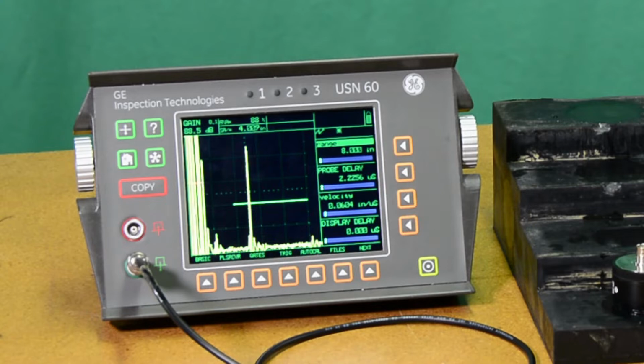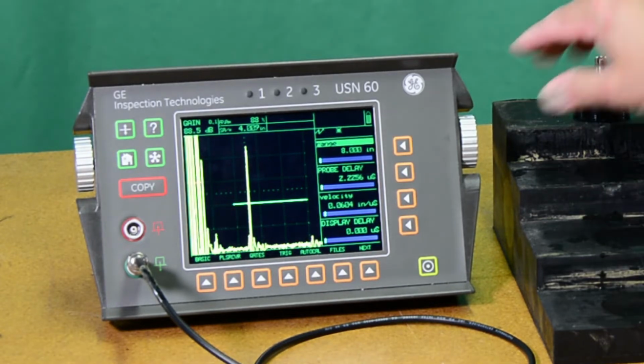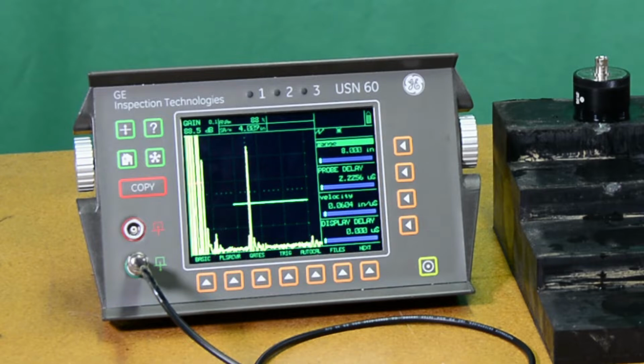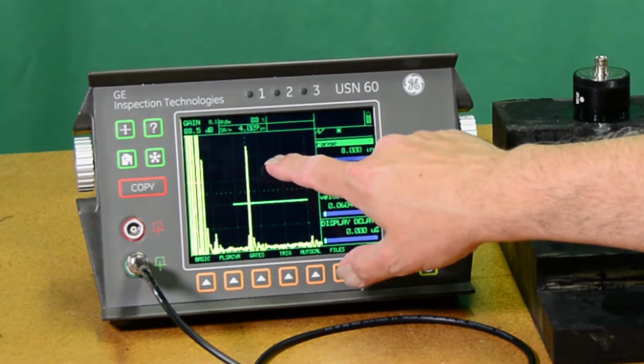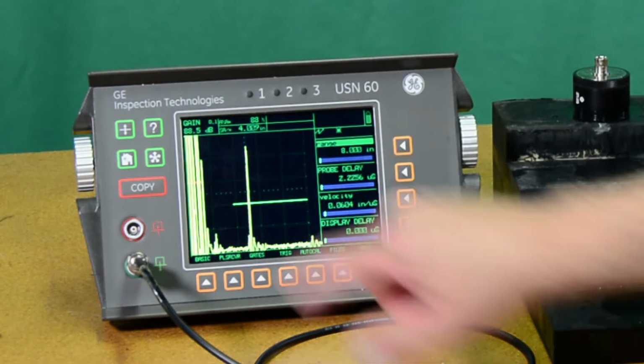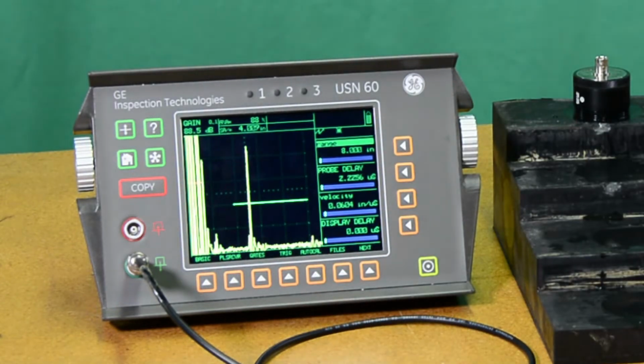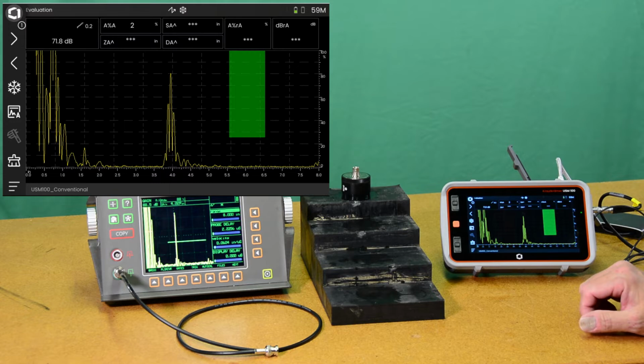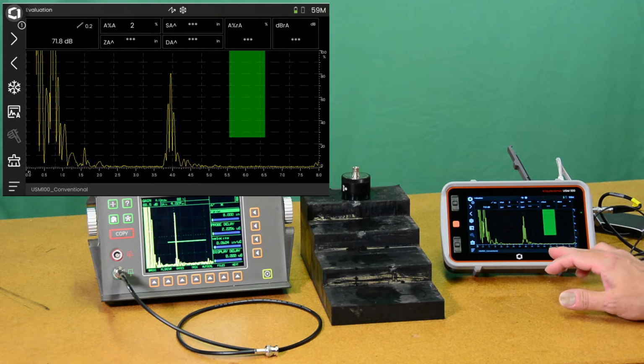On the screen I have frozen the signal from the instrument optimized for setup with this probe, looking at the 4-inch thickness of the rubber step block. We won't go through the full setup for that. We'll go through the USM 100 setup here in a few minutes. But that gives you a reference signal. You see the echo at 80% full screen height, actually a little over about 90%, and gain set at 88.5 dB to accomplish that. Over here on the USM 100, I have also optimized setup for that.